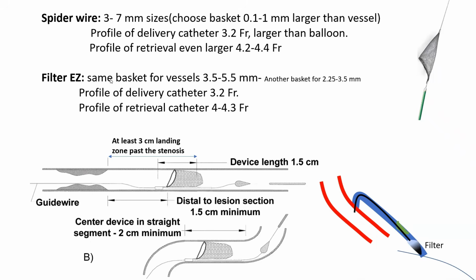The FilterEZ has the same basket for all vessels, 3.5 to 5.5 millimeters, and it has another basket for smaller vessels, 2.25 to 3.5 millimeters. Those are sizes that are not available with a Spiderwire. The profile of the delivery catheter is almost the same, and the profile of the retrieval catheter is almost the same as the Spider catheter. One difference is that the FilterEZ has a straight retrieval catheter. It also has a bent tip retrieval catheter that may be advantageous in difficult cases, as I will describe.